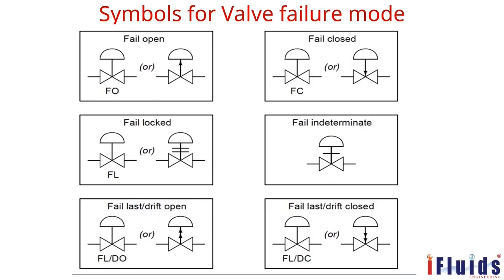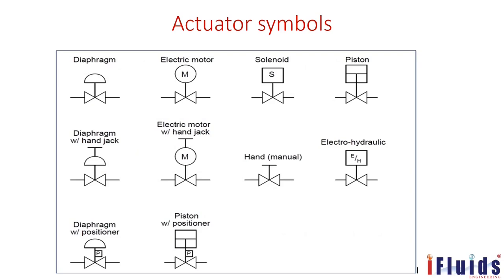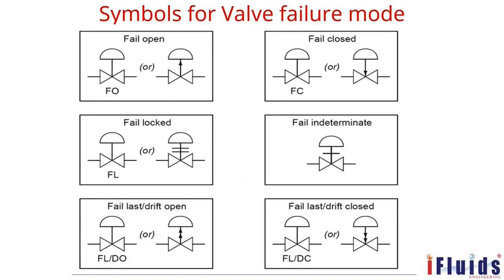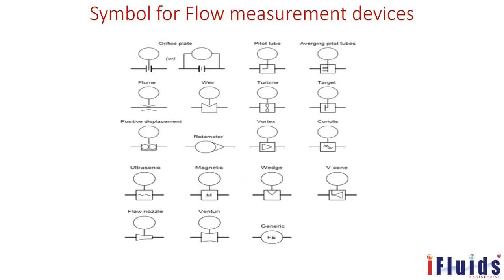Symbols for valve failure mode: below each valve symbol you have to show FO (fail open), FC (fail closed), or FL (fail locked). When there is an instrument error, signal failure, or power failure, the valve goes to open or closed position as specified. This must be mentioned in the P&ID.